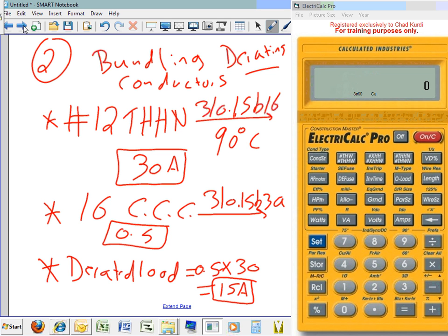So now, Ashley, what do I do? I count 1, 2, 3, 4, 5, 15 fixtures at 1 amp per fixture, and stop. Done. The reason I like this example, guys, is because this is very common in commercial and industrial. It gives you an idea of the power of grouping conductors as they come out of the panel. So yes, we put 16 current-carrying conductors, we cut it by half, but we still got 15 amps out of number 12, which is great, because I can only pull 16 amps out of every circuit. So I lost only 1 amp.